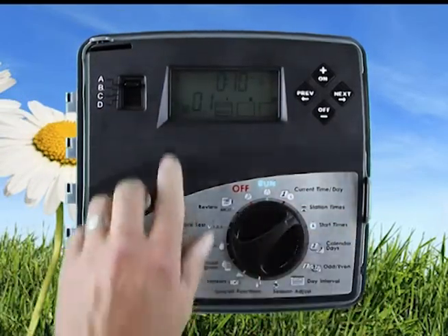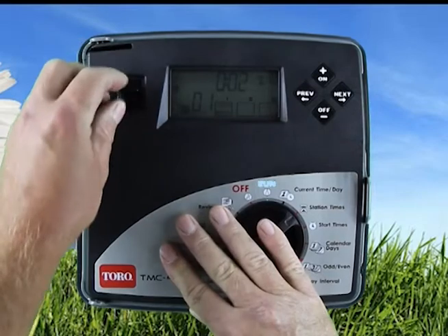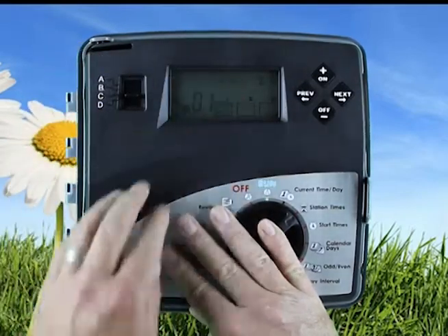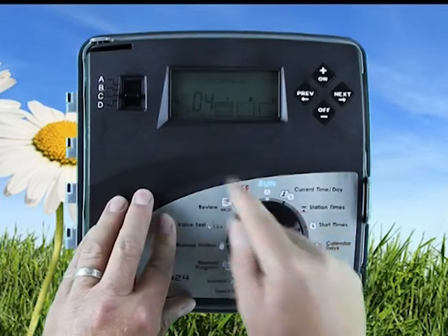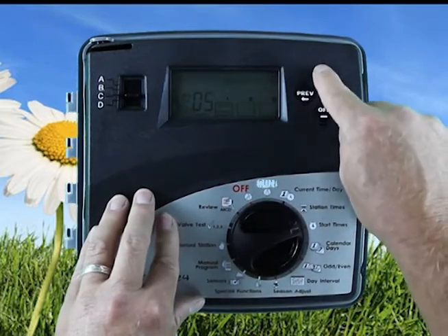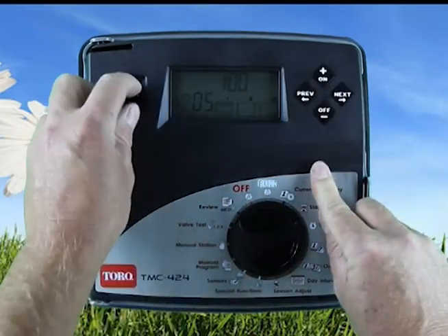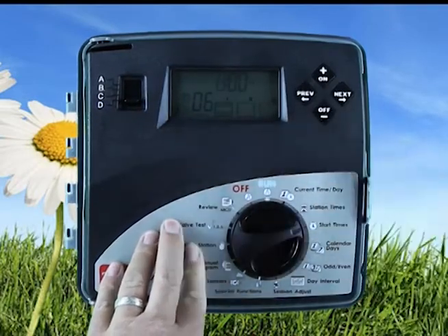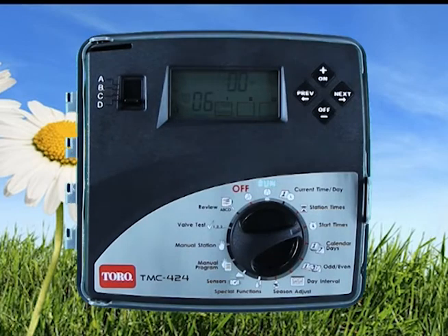So as you can see, A, B, station 1 would be for 2 minutes. C, nothing's been selected. There's no start time, but that would be a 4th start time. And I could go and make a 5th start time. See, and then D would be a 6th start time. Okay? So it's just like 4 different controllers. Each controller has to have a start time, a station time, which is the duration, and the calendar days. What days do you want it to water?